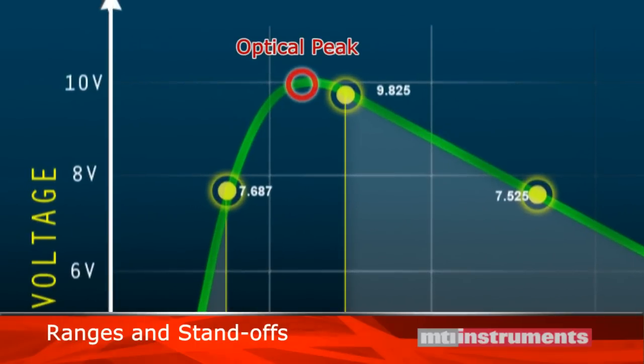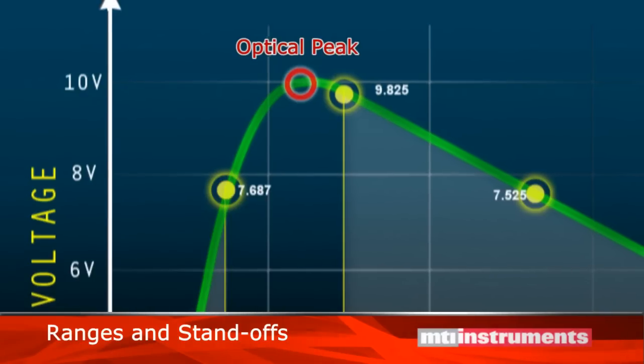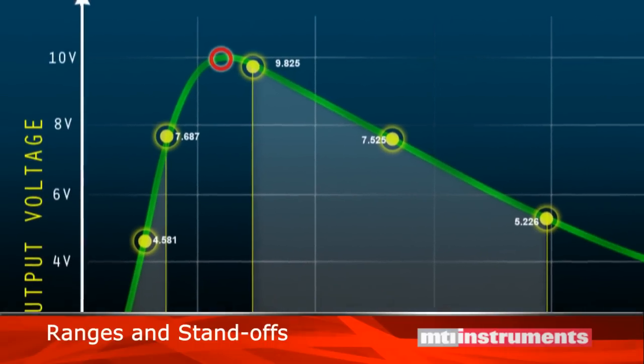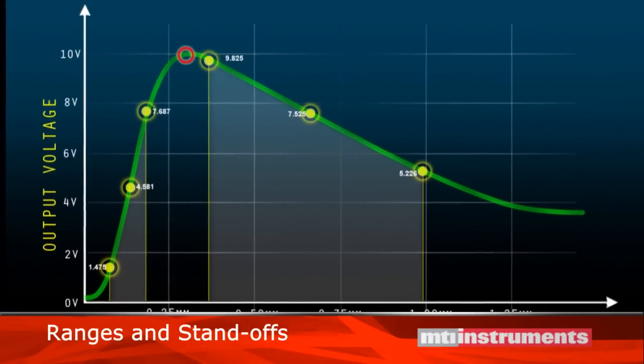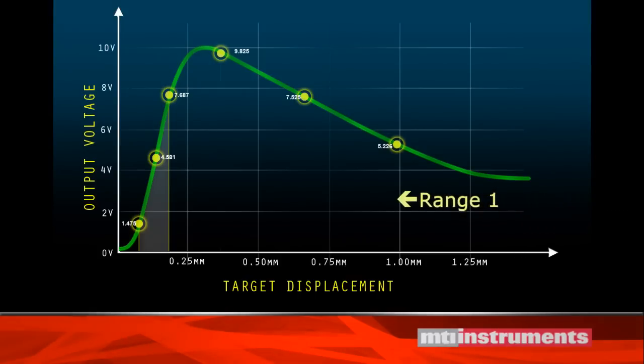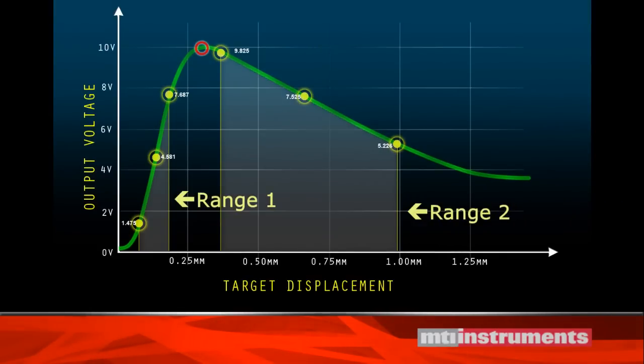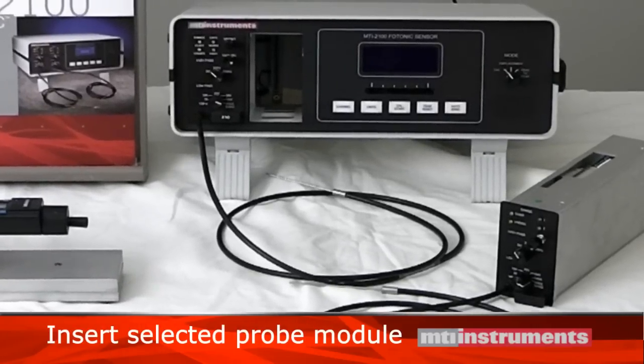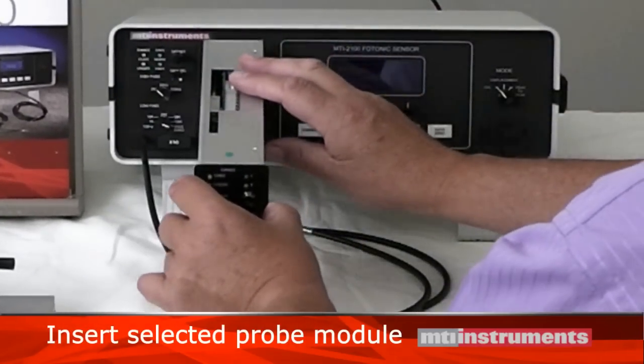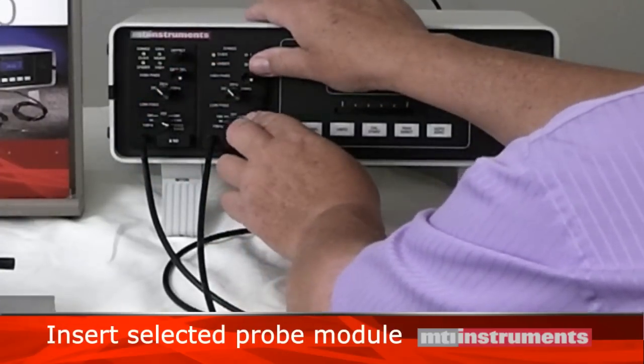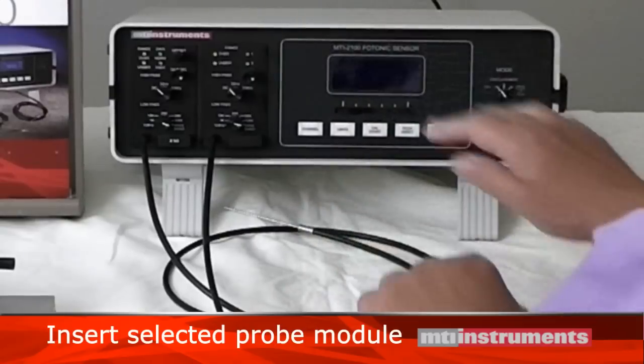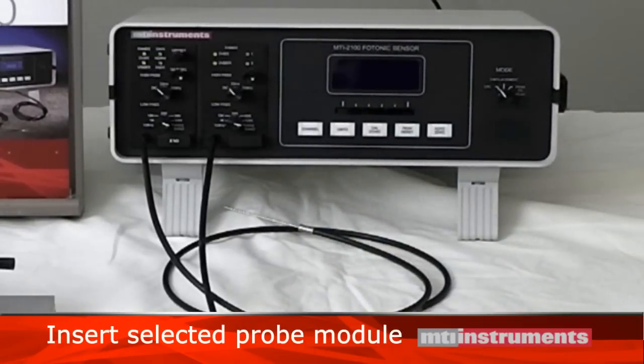within range. The optical peak is the standoff distance where the maximum amount of light is reflected and received from the target. It is interesting to note that the optical peak occurs at the exact same standoff distance for virtually all surfaces. This is important because it is used during the calibration procedure to set the range 1 and range 2 parameters. First, we insert the selected probe module into the bay. It is a fairly snug fit, so some pressure may be needed to make it seat snugly into the rear connector slot. The probe module will operate in either bay.